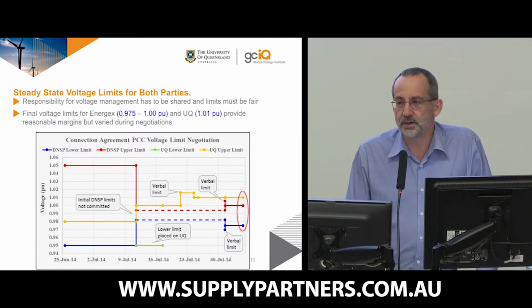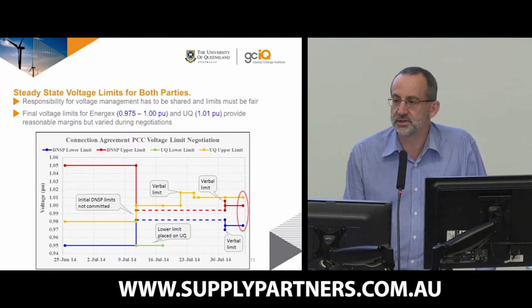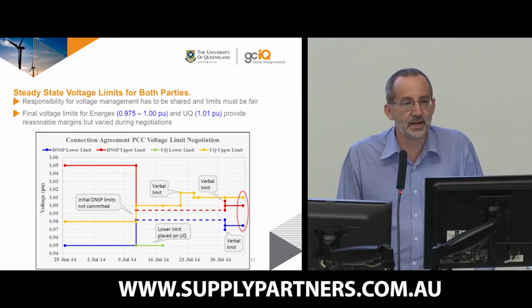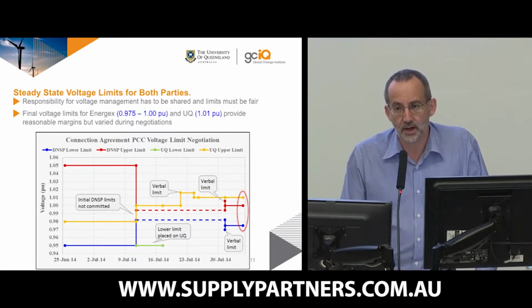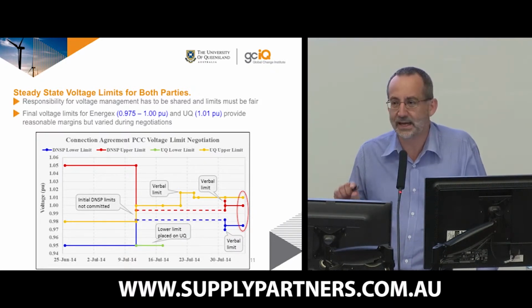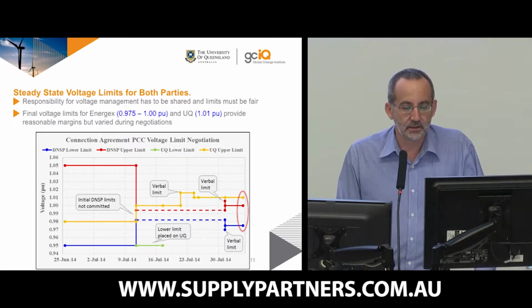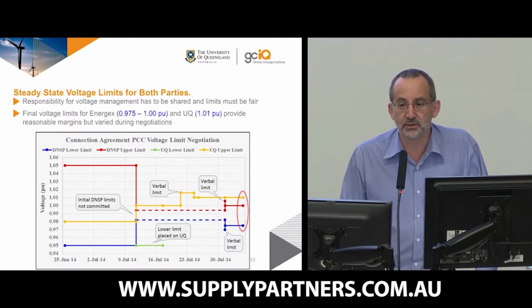So that was quite an achievement. As you probably realise, across the network, the utilities are allowed in Queensland a 10% variation on the 11 kV, the 11,000 volt network. That's quite a wide range, and they need that wide range, but they don't want to be varying that range at any point on the network. And in fact, they still need to be controlling it fairly tightly at any particular point. So Energex ultimately agreed to hold the voltage within 2.5%. And when we come on, we've agreed not to raise it by any more than 1% above that.